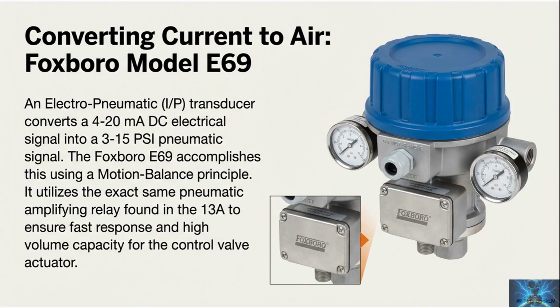Converting current to air: Foxboro Model E69. A current to pressure transducer converts 4 to 20 milliamps direct current into a pneumatic signal. The standard pneumatic output is often 3 to 15 pounds per square inch for valve actuators. The Foxboro E69 does this using a motion balance principle, not force balance. It also uses an amplifying relay, so the output can move a real actuator quickly without lag. This is one of the classic bridges between electronic control signals and pneumatic final control.